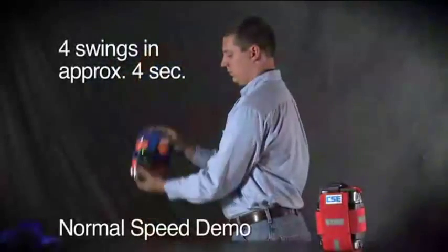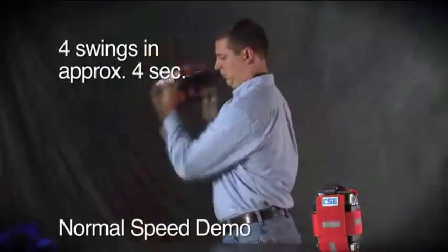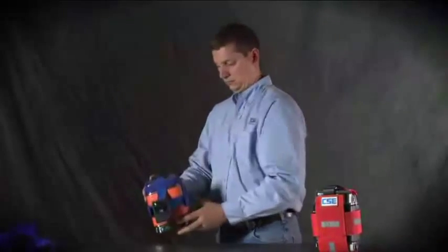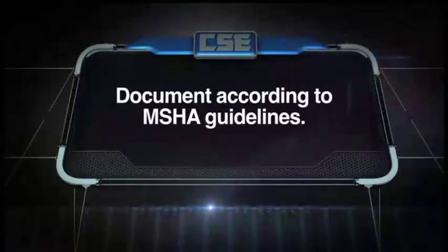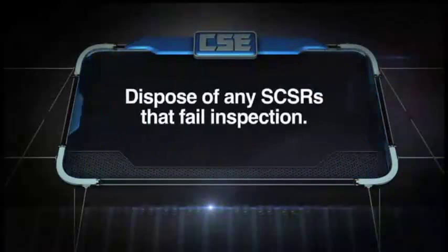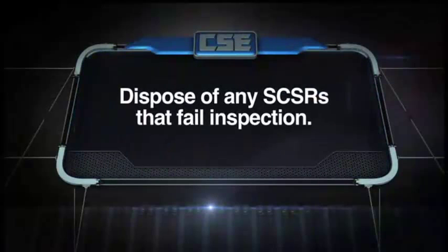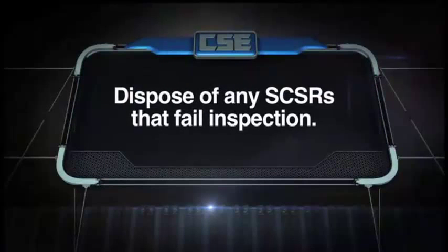If the red light flashes once or twice during the first or second swing, the SCSR still passes. Return it to service. If the red light flashes or glows steadily throughout the test, the SCSR fails. Document each inspection according to MSHA guidelines. Dispose of any SCSRs that fail inspection according to your company's policies.